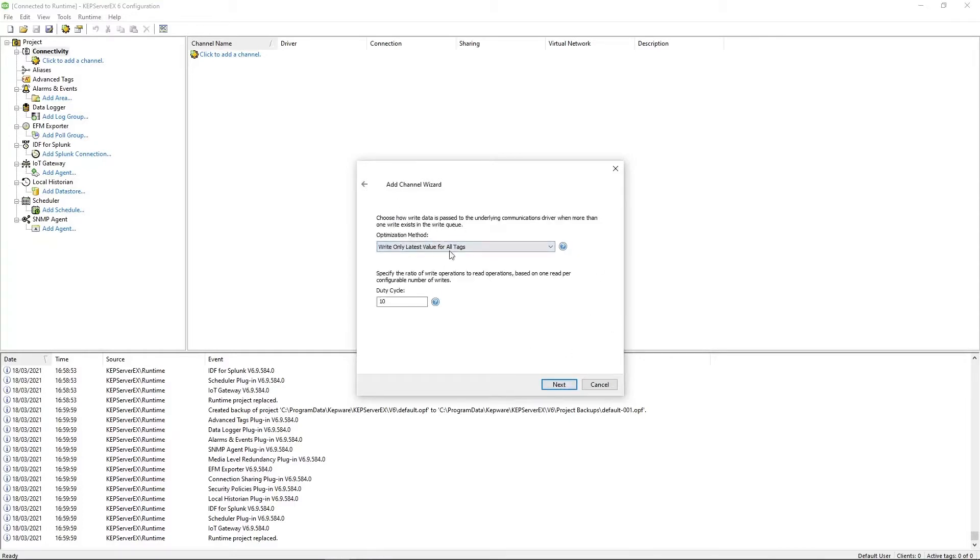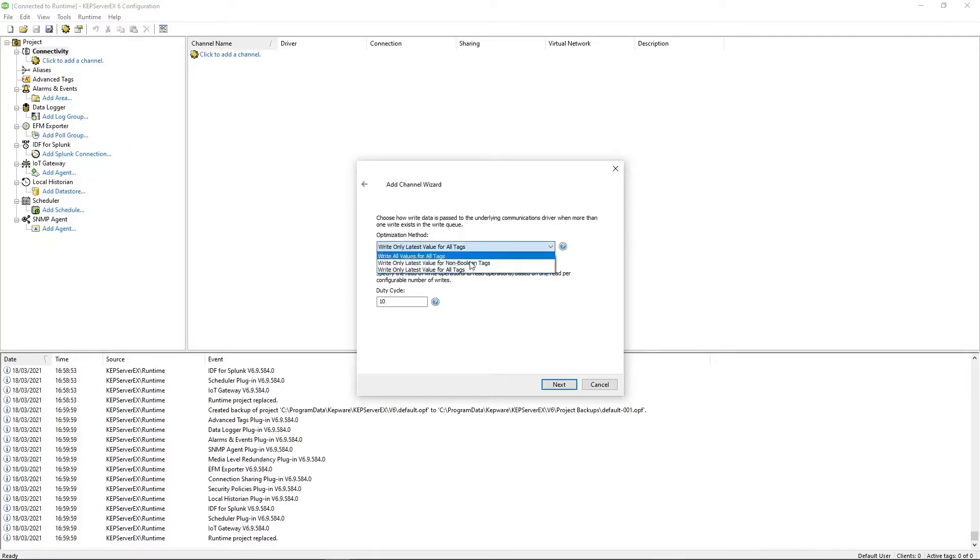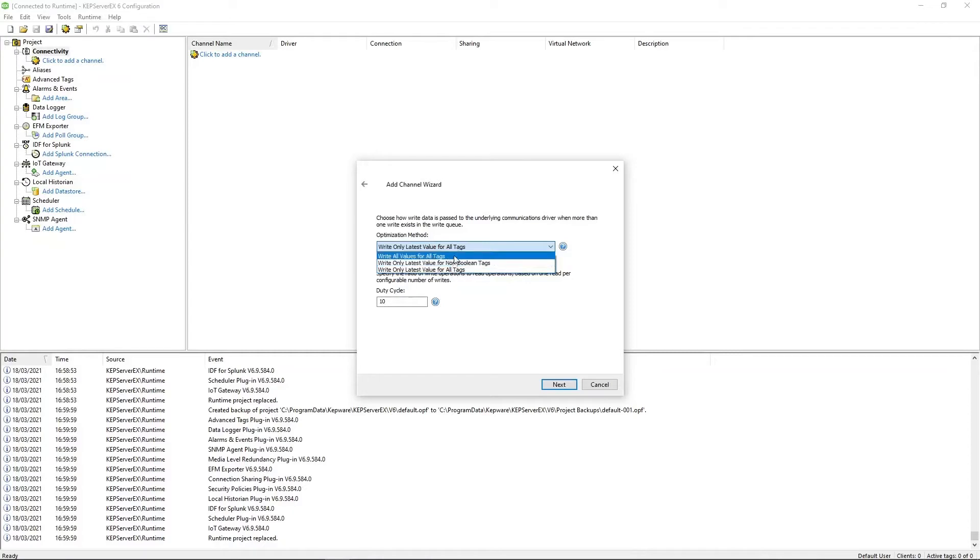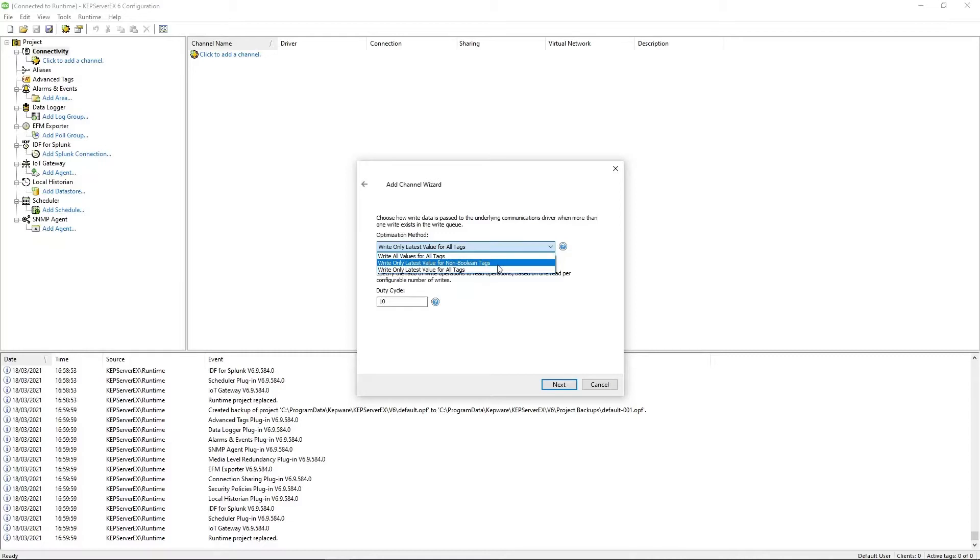This page lets you deal with how to handle multiple writes that are queued in KEPServerEX. So let's say you press a button five or six times, but those writes haven't yet gone out to the PLC. In a lot of cases, you might only need the most recent write. So you don't need all six to go out, you just need the most recent one, in which case the default of write only latest value would be the option. But in some cases, you may actually need every single one of those writes to go out to the PLC, in which case write all values for all tags would be what you need. And there's also an option for write only latest value for non-boolean tags.